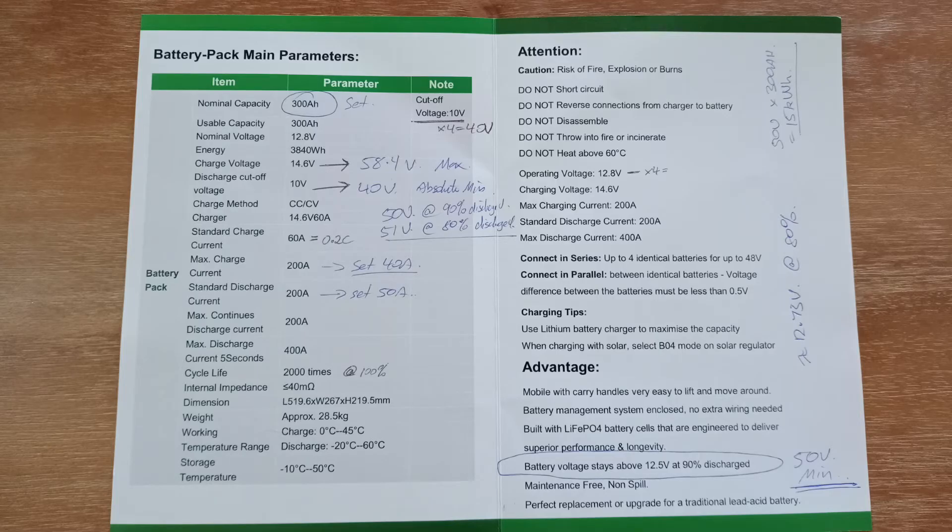There's a booklet containing the battery specs which go into the SunGrow inverter. The modules are connected in series, so the total pack is 300 amp hours capacity. The charging voltage is 14.6 volts times 4, which is a 58.4 volt pack charging voltage. The discharge cutoff voltage is 40 volts, but I'm using 48 volts which is a very safe value. My end of discharge value is 50 volts, which represents 90% discharge and 12.5 volts per module.